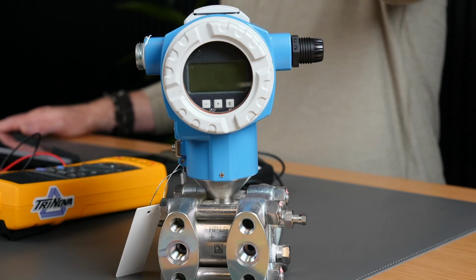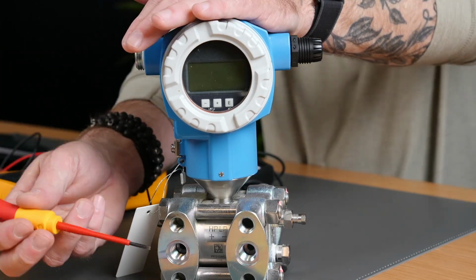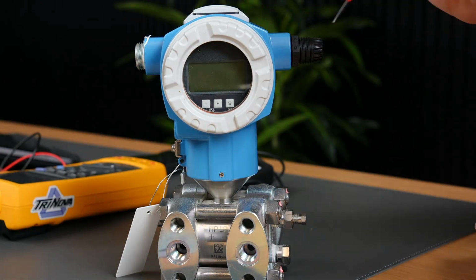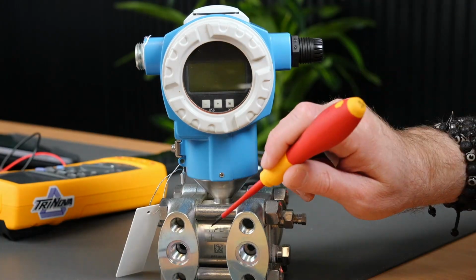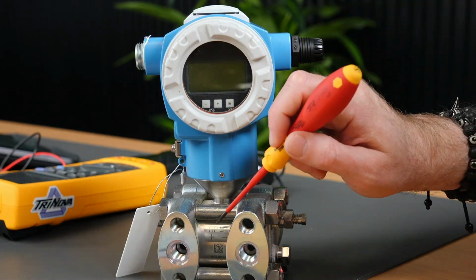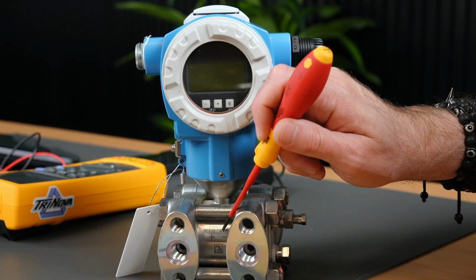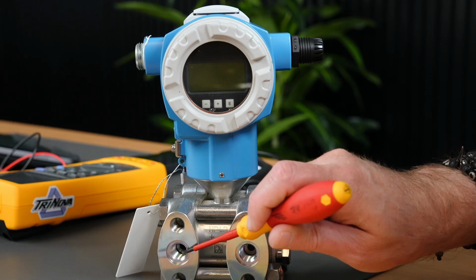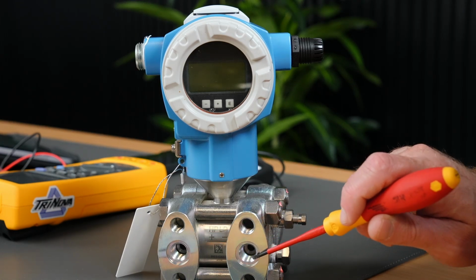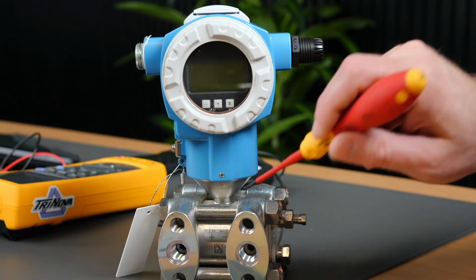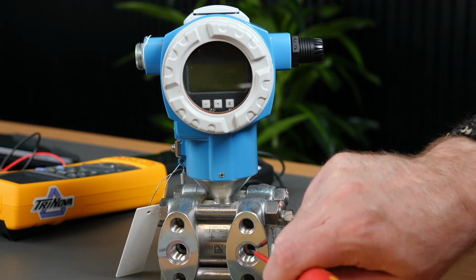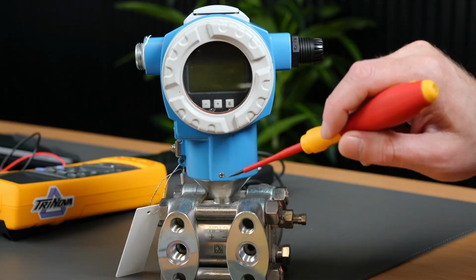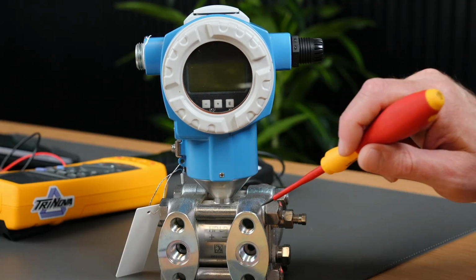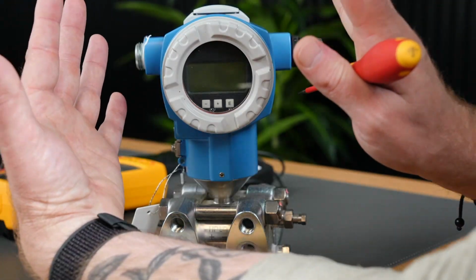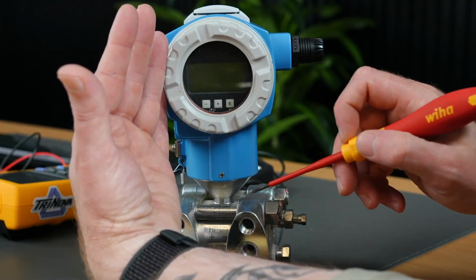So what I've got sitting out on my workbench here is a differential pressure transmitter. Hopefully you can see this as I come around this way. I've got the high port side here, and this actually has both indications on it. It's got an HP and an LP with a plus and a minus underneath it. So high side, low side of my transmitter on my pressure cell, and then this is a diaphragm on this side, diaphragm on this side, and we're sandwiching or wedging that together. I always thought about that kind of like a wafer. We're pressing that together with a diaphragm on both sides.